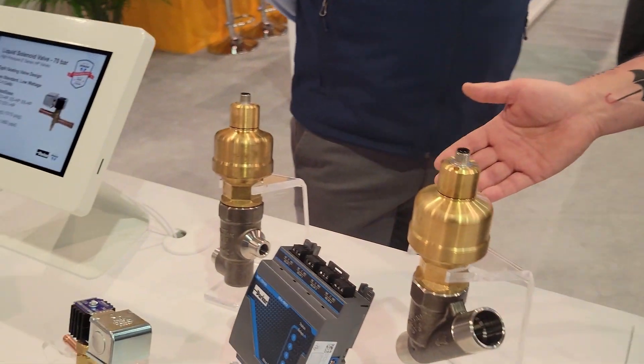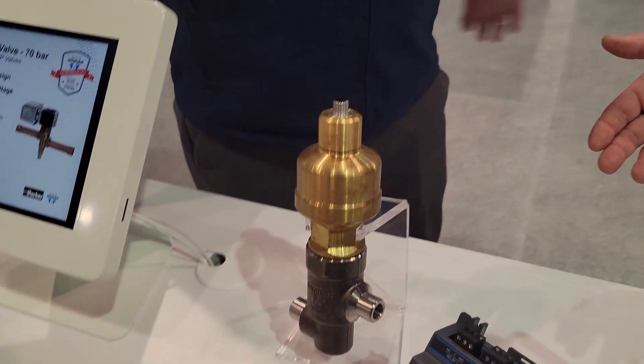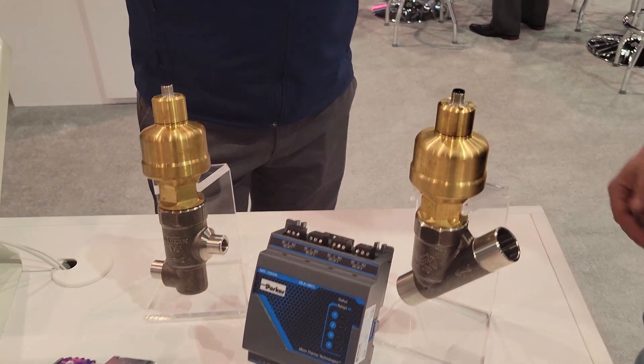This is the flash gas regulator, and it's typically running at around 515 psi. That's what actually takes the pressure off the flash tank and creates that liquid in the flash tank. It's awesome to see that you guys are being innovative and coming up with things that are needed for the industry.